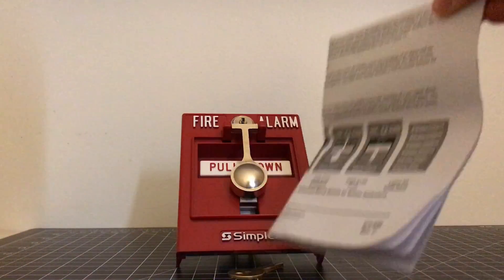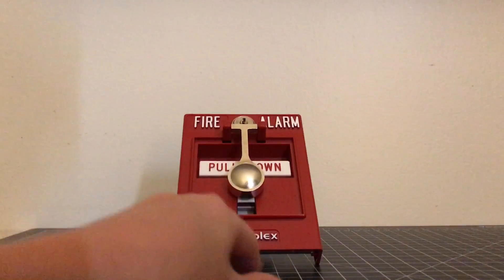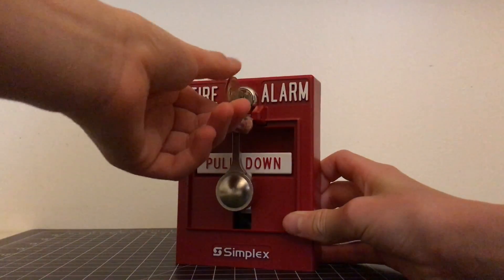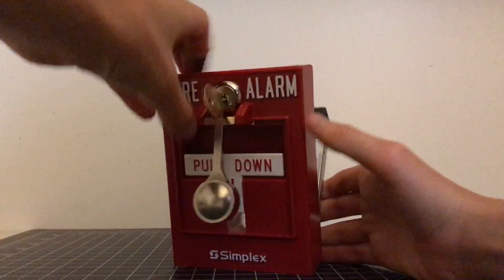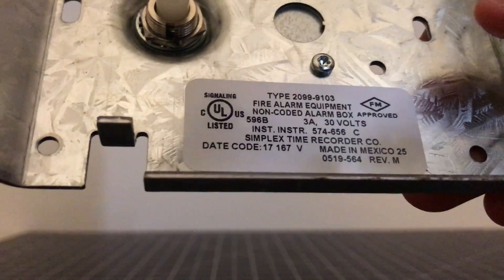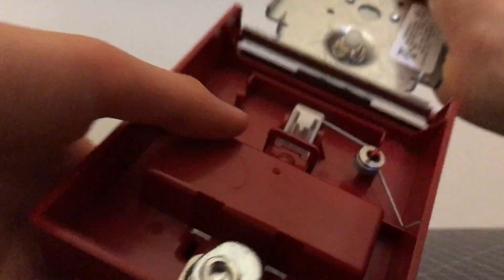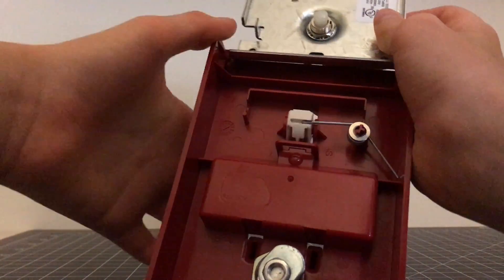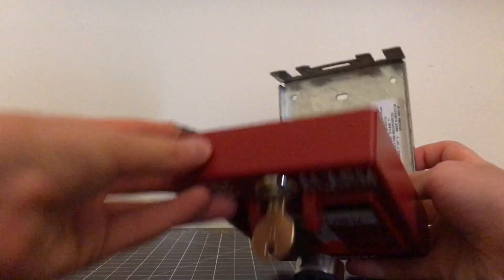So we're going to go ahead and open up this pull station to show you the inside. We're not going to read through the manual, but it has a lot of information on how this unit works. You use the B key to open it up — stick it in, and then on a lot of the newer ones you turn to the right instead of the left. Turn it right and unlock the pull station. Here's the inside — right here is the model number 2099-9103. It has the date code, and this is just a regular button in here. You have a button, and then a little lever right there that's spring-loaded, and right there is the little spot for the knocker.